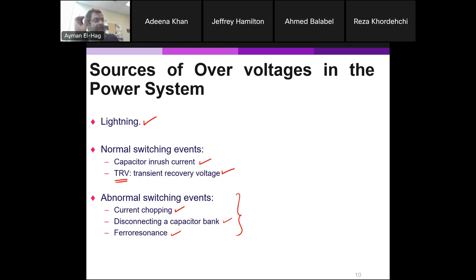Now, there are two different things here when it comes to protection of power system assets. One is that the manufacturer should design the asset to withstand certain high voltages. But the utility also has to ensure that the surge voltages do not exceed what the manufacturer is supplying. For example, if I supply you a transformer that can withstand a 95 kV lightning surge, the manufacturer should design a transformer able to withstand this. However, the utility has another obligation, which is to make sure that no surge of more than 95 kV makes it to the transformer. So we have to provide certain protection mechanisms to ensure that. This will also be covered next week.